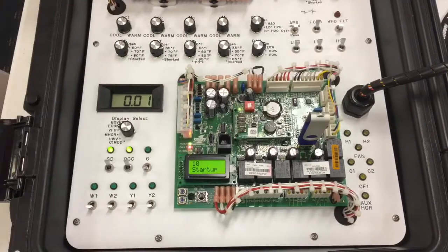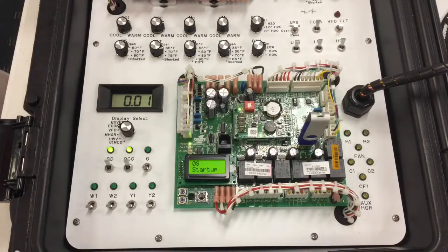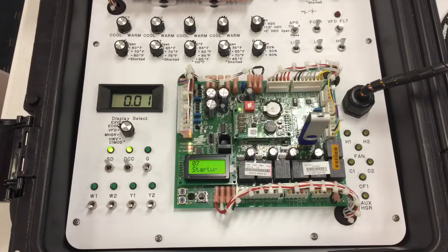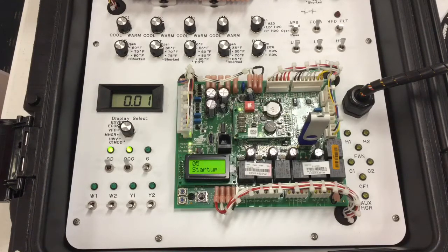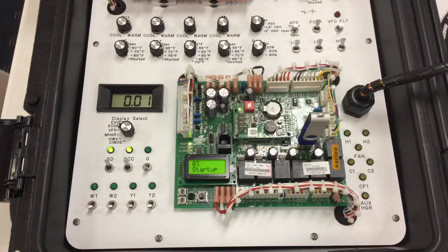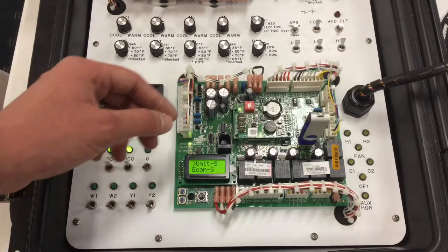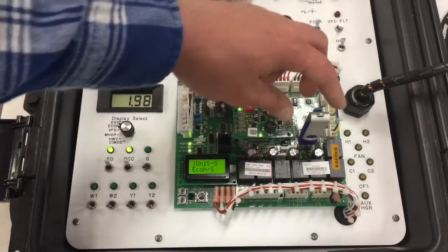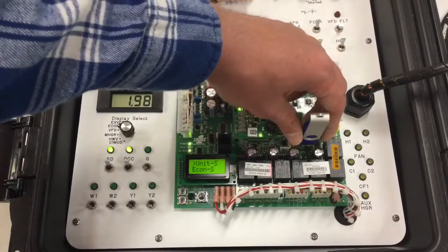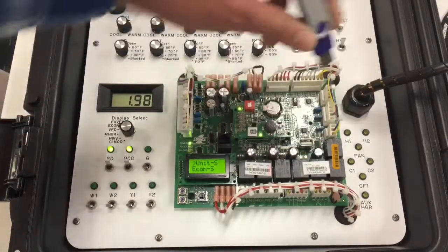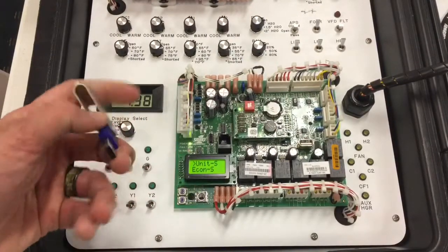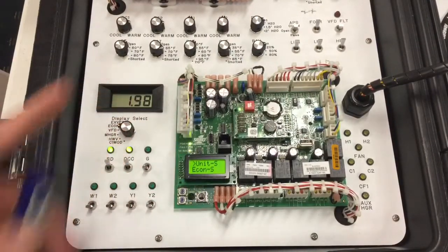Now that we're nearing the end of our countdown sequence from the 120 seconds after a restore has been done to the control board, the five minute anti-short cycle time delay will begin to initiate once again. You've successfully completed a restore and a backup onto the new control board and off of the old control board. You can now remove the flash drive from the unit control board and put it away for later use.